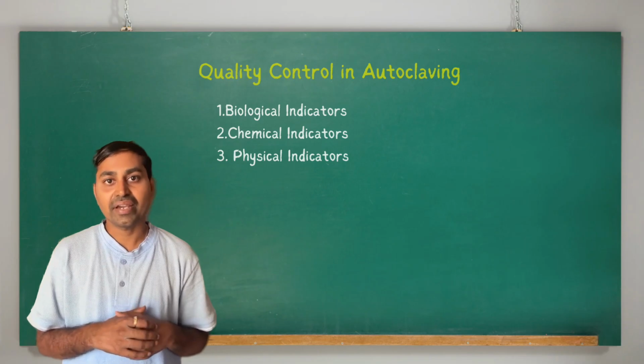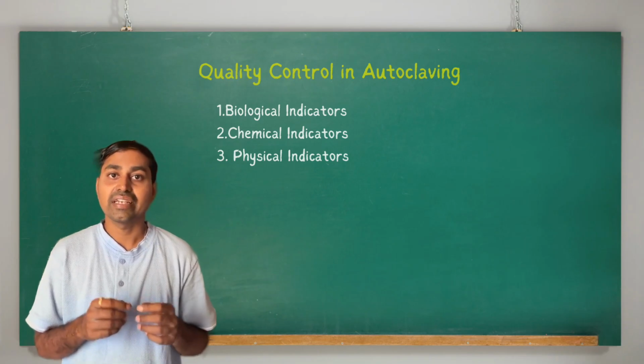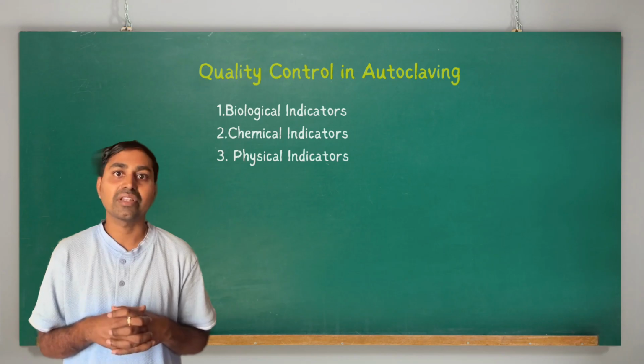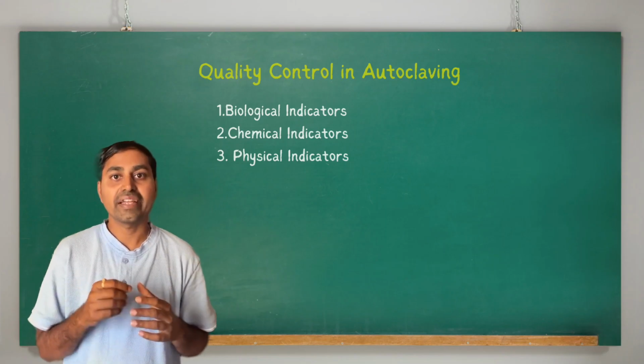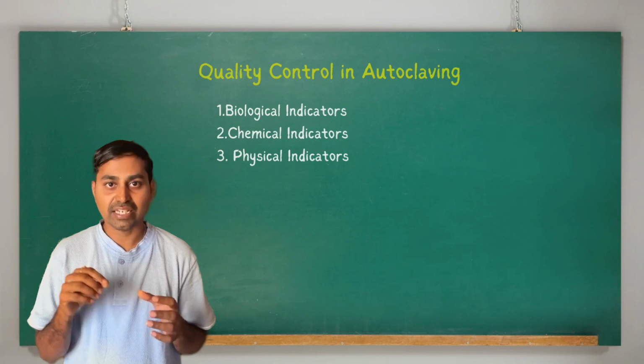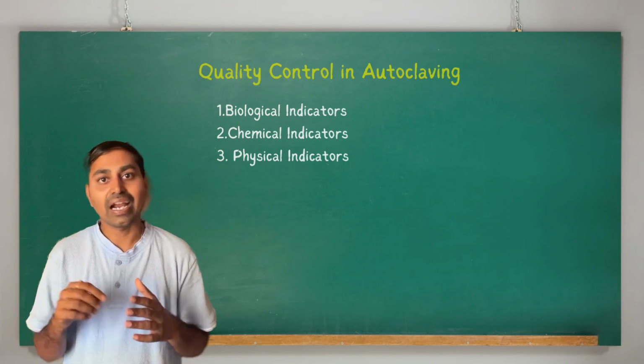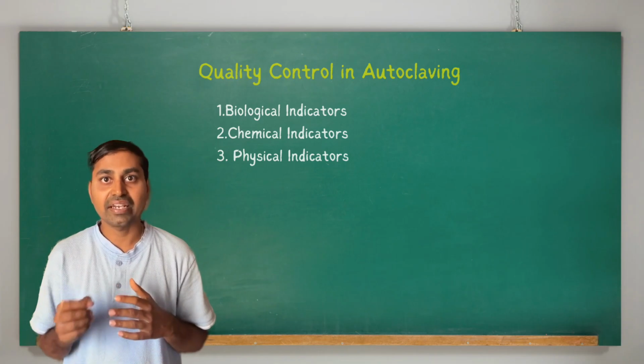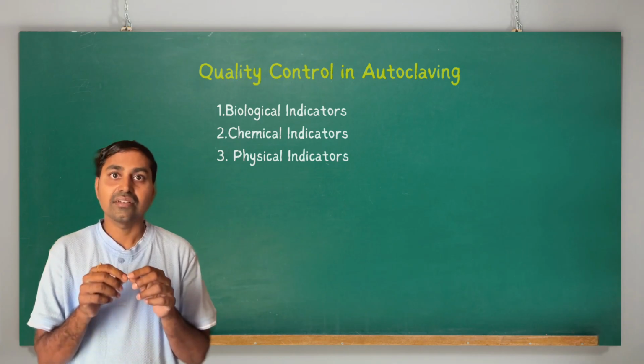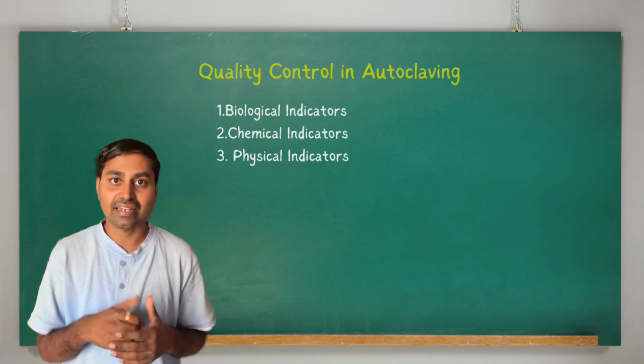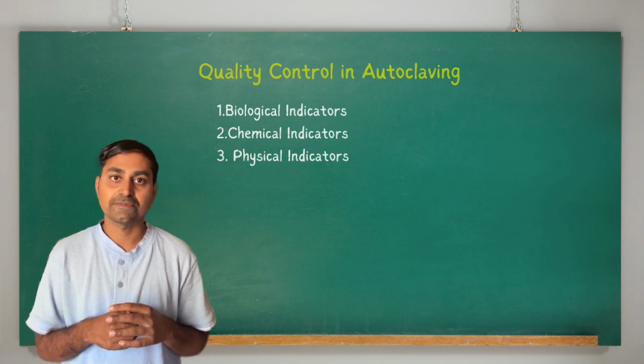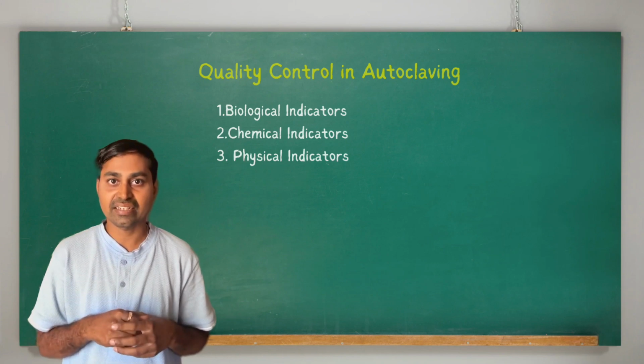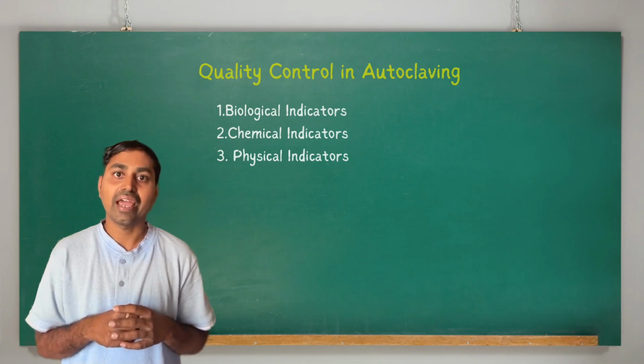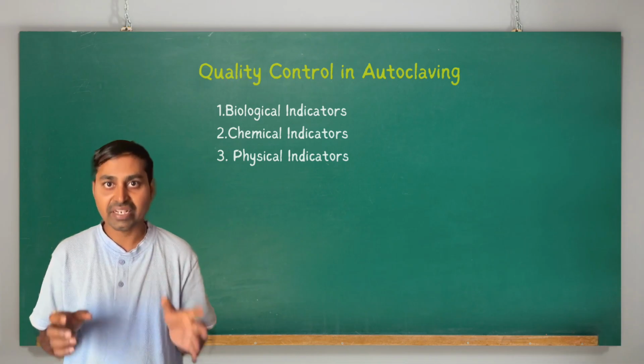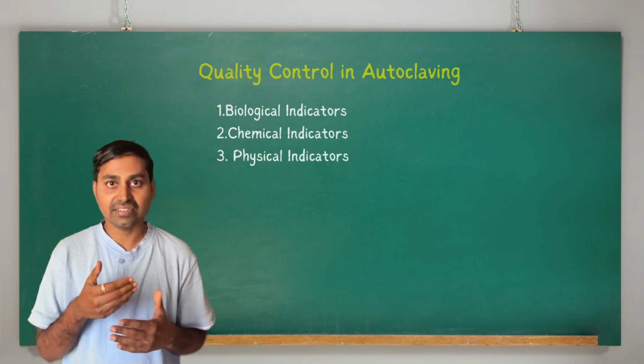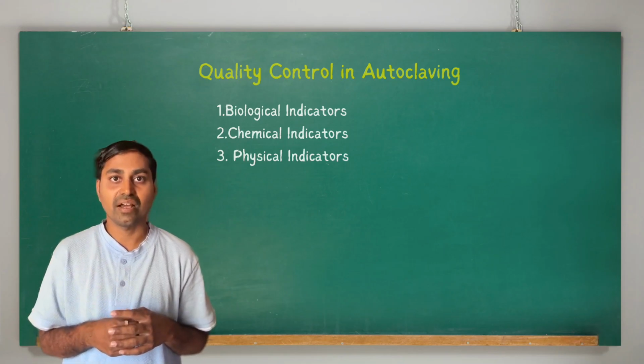Then the second one, chemical indicators. Here we stick paper tapes over the instruments to be sterilized. The tape changes color if it is exposed to heat or autoclaved. Then the third one, physical indicators. Here we check temperature and pressure gauges. This is also an indicator. These are the three indicators for quality assessment of autoclaving.